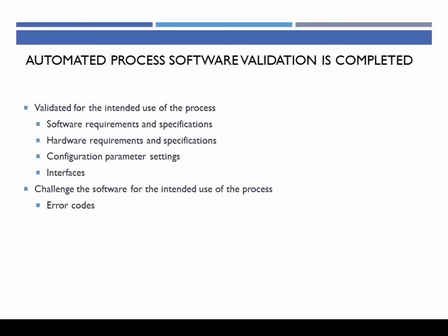You demonstrate that the software is compatible with the hardware. You know what the configuration or version of the software is. You know that it interfaces properly. And you want to challenge the software and see if it does what it's supposed to do. If the machine is running along and you open the door, does the software shut it off? Do you get an error code that tells you what happened?